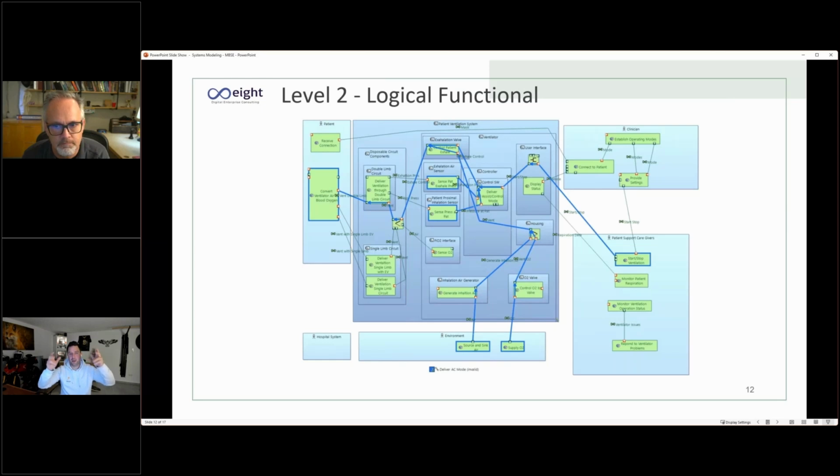We are turning in a vertical way because we break down, we decompose the functional chain, and we decompose the system. We still have the system in the middle, and now, because of the decomposition, we add several parts of the system. And when we start with the functional chain again on the right, with the start-stop of the ventilation from the patient support caregivers, Larry will highlight it. Then you will see that the box is then connected to the user interface.